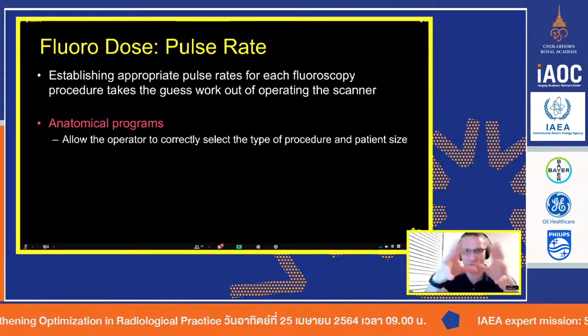it's correct for the right size patient. And so we need to make sure the pulse rates make sense for what we're doing. In a video swallow, we're going to have a higher pulse rate. If we're doing a line placement, a PICC line or something, we don't need a lot of pulse rate. We can even do pulse rates down to 3 pulses per second or 1 pulse per second. We need to set the system so it has the right kind of filtration.